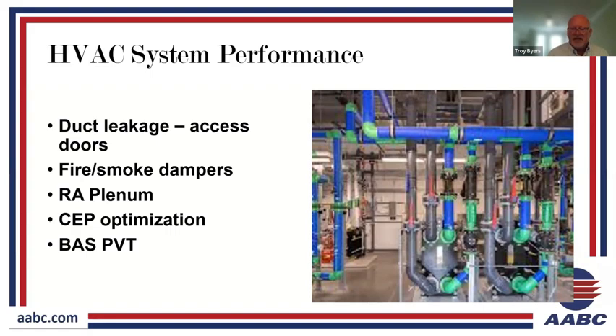Central energy plant optimization could be a whole project in and of itself, where optimization systems are continuously monitoring and analyzing real-time data from various sources, such as your building loads, your weather conditions, even utility rates, to make real-time adjustments to equipment operation. And so the system can adjust the sequencing, the staging, and load sharing to achieve the most efficient operation and the lowest cost for given conditions. Pretty advanced stuff with some pretty intense algorithms that make that work. But without it, you're not going to get that efficiency.